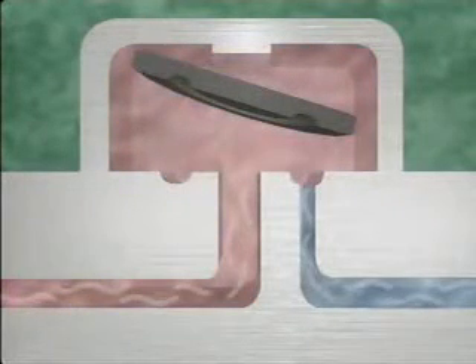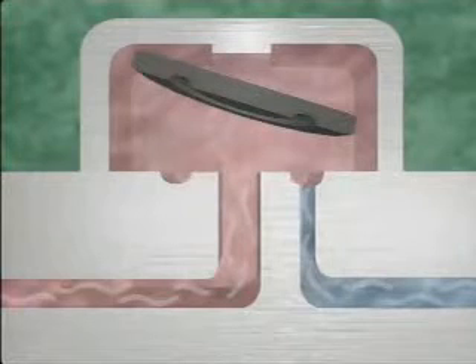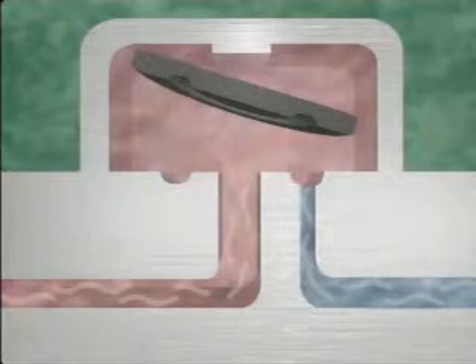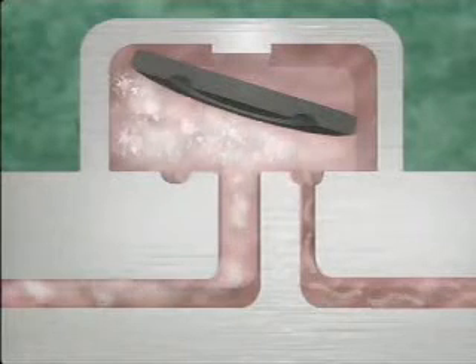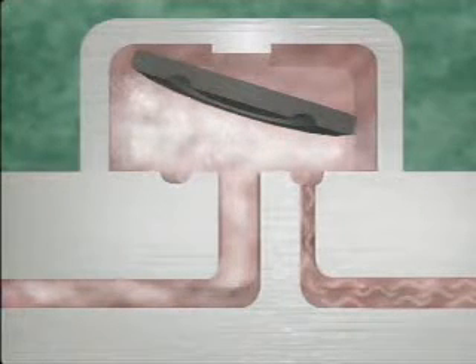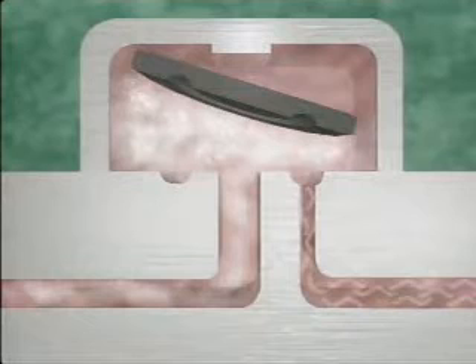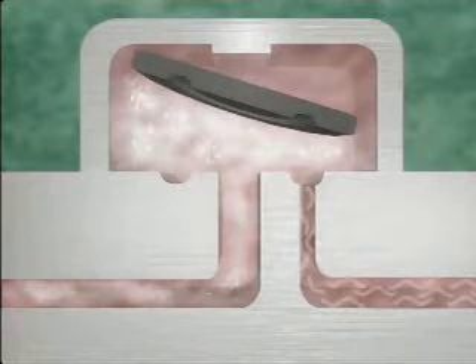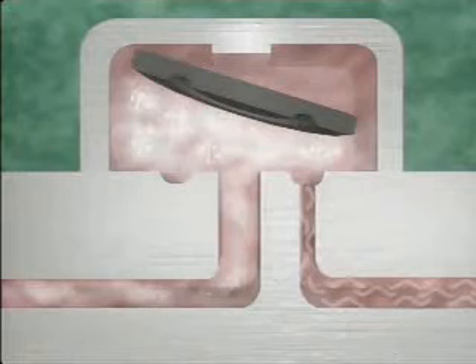During normal operation, hot condensate entering the trap experiences an increase in velocity and a reduction in pressure. As a result, some of the liquid condensate changes state, flashing to steam. Because steam has a greater volume than an equivalent weight of condensate, the velocity of the flow through the trap greatly increases after the flash steam has been generated.